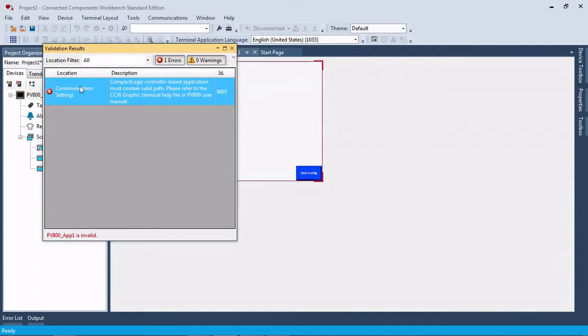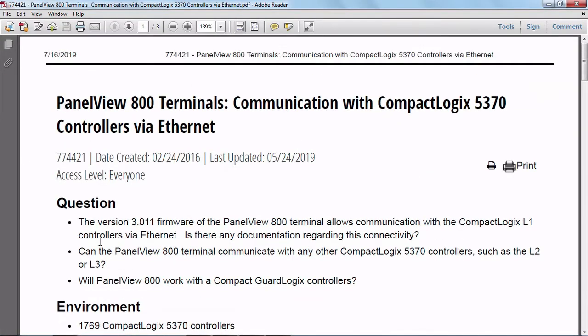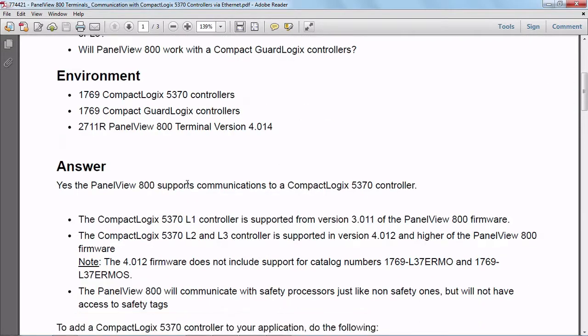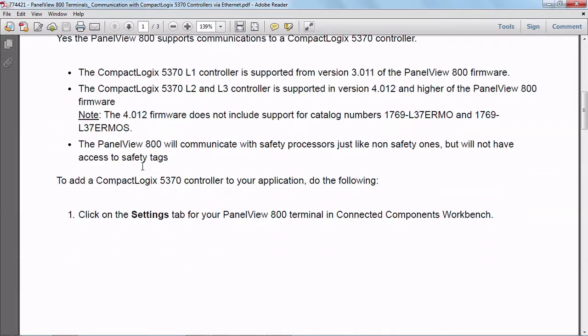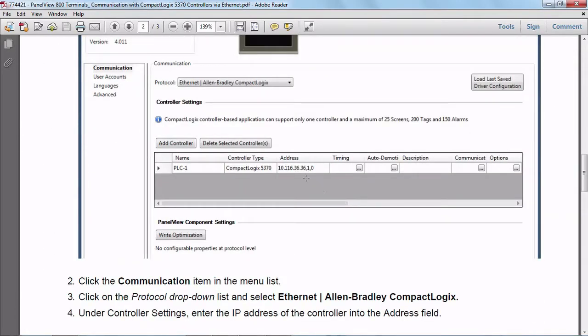So if you were to search this on Knowledge Base, this error code, you would end up finding this Knowledge Base article, 774421, where it tells you how to set up the communications path to the CompactLogix, and what it will tell you is that you have to have the comma one comma zero in your address, in your IP address.